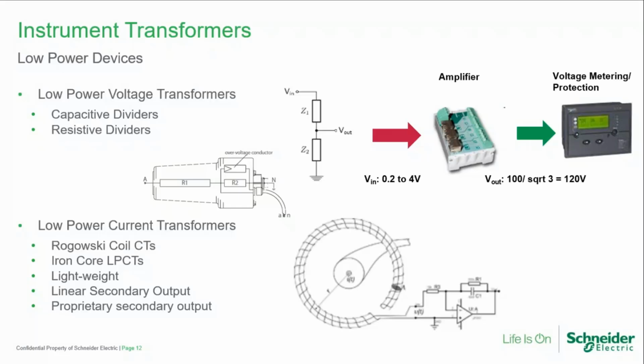With things like Rogowski coil CTs or even iron core LPCTs, they have linear secondary outputs, so that for the entire range of application, you're going to get a very accurate reading. Whether you're reading at 100 amps or 600 amps, you're going to get much more accuracy out of the newer designs of CTs.